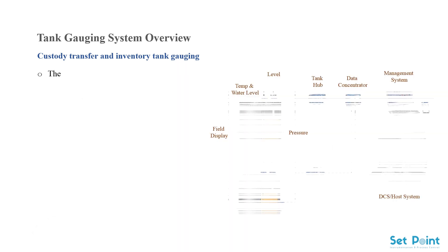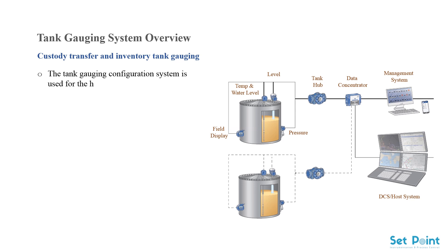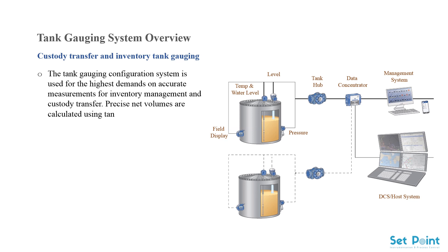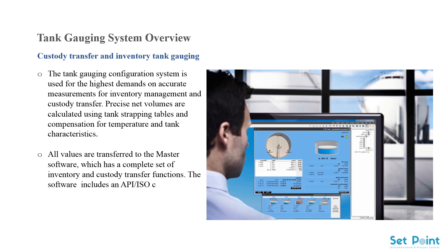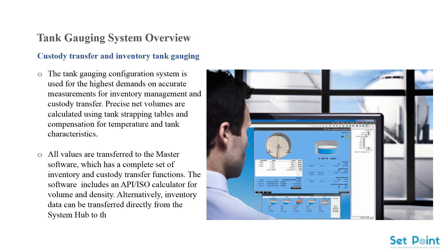The tank gauging configuration system is used for the highest demands on accurate measurements for inventory management and custody transfer. Precise net volumes are calculated using tank strapping tables with compensation for temperature and tank characteristics. All values are transferred to the master software, which includes a complete set of inventory and custody transfer functions, including an API/ISO calculator for volume and density. Alternatively, inventory data can be transferred directly from the system hub to the DCS without going via software.